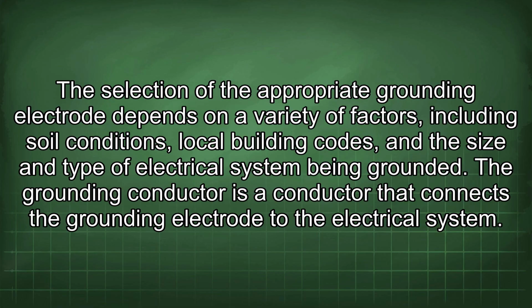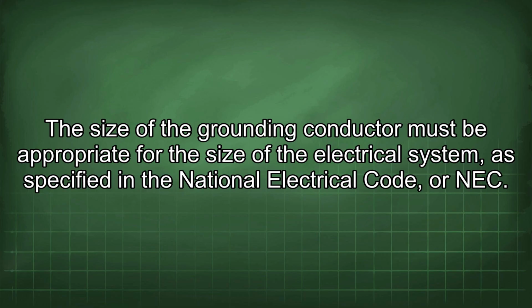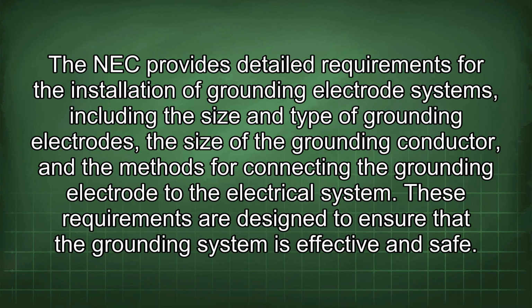The grounding conductor is a conductor that connects the grounding electrode to the electrical system. The size of the grounding conductor must be appropriate for the size of the electrical system, as specified in the National Electrical Code, or NEC. The NEC provides detailed requirements for the installation of grounding electrode systems, including the size and type of grounding electrodes, the size of the grounding conductor, and the methods for connecting the grounding electrode to the electrical system. These requirements are designed to ensure that the grounding system is effective and safe.